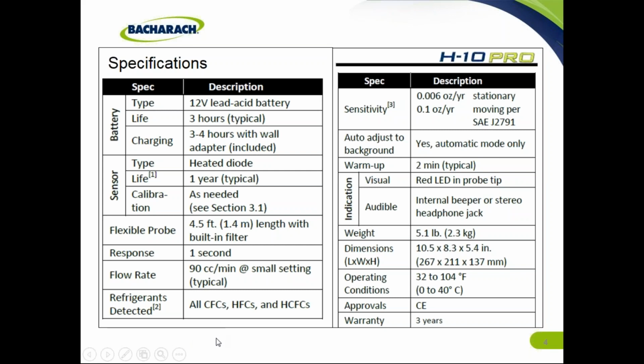It has a 4.5-foot probe with a built-in filter. This unit also has a pump inside of it, and it pulls air through that probe to the sensor. Response time is about 1 second. Flow rate is about 90 cc's a minute. We talked about the refrigerants it detects. Here are the sensitivity levels we'll go over. It does have an auto mode. We'll adjust our background gases. It has a 2-minute typical warm-up.